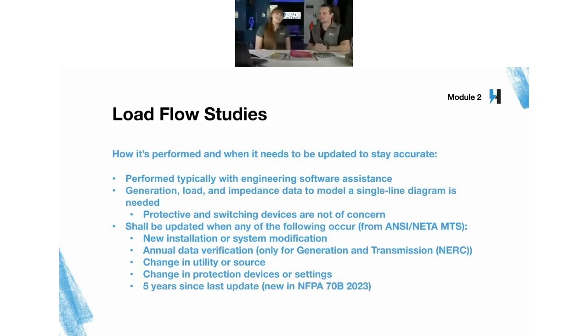When do you need to update it? Pretty much the same as what we've been saying all along: every 5 years at a minimum, but it shall be updated anytime there's a change that could affect the results of the load flow study. That 5 years really is a minimum.